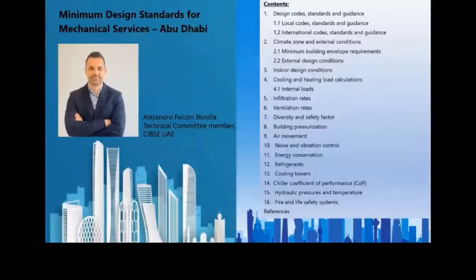It's worthy to point out that the guide mentions how the Abu Dhabi International Energy Conservation Code, in its chapters 4 and 5, encourages the mechanical designer to minimize energy use through strategies such as variable frequency drives in fans and pumps, high efficiency energy recovery systems in fresh air units, and demand control ventilation in spaces where occupancy is 40 persons per 93 square meters and in spaces larger than 50 square meters. In general, it sets a low carbon footprint emission mindset in the designer.